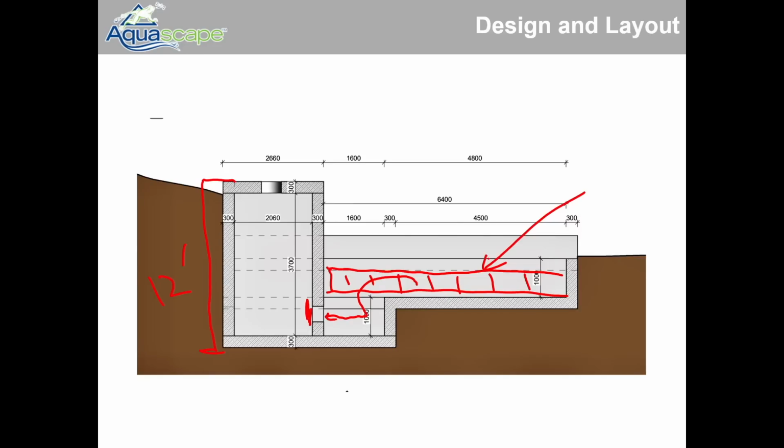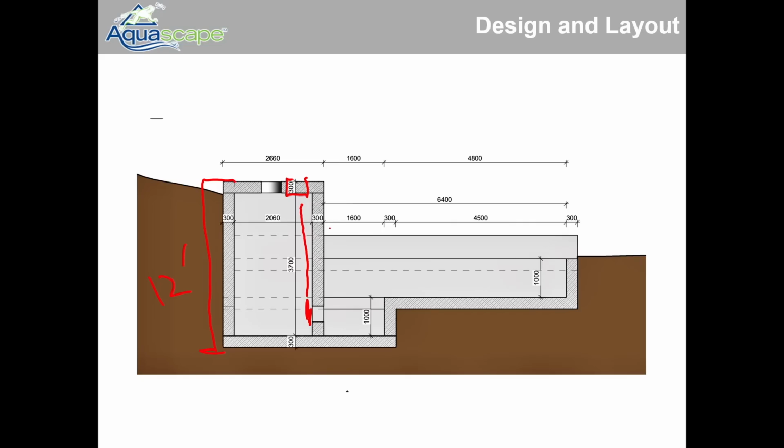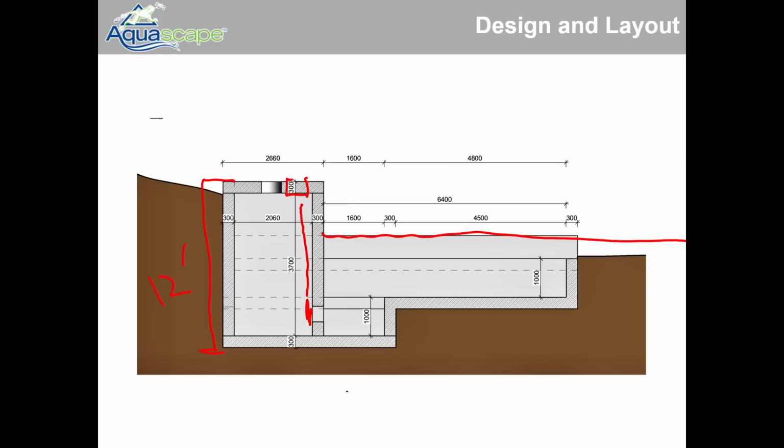What the purpose of this is, somebody could open a manhole up here on the top and actuate this valve. This becomes very, very important from a maintenance standpoint, because this is connected to that main lake, which is giant. It's millions of gallons of water in the top foot. If you ever have to get to the pump, and the normal lake level is high enough, you're going to be putting on a scuba suit and going down to work on this pump. It's going to be very difficult and challenging. So this valve is critical, because now you could shut off the water from this entire lake system just by closing this valve over here, and that will keep this one side flooded. Then this water you could drain all the way down, allowing access to do maintenance on the pump.